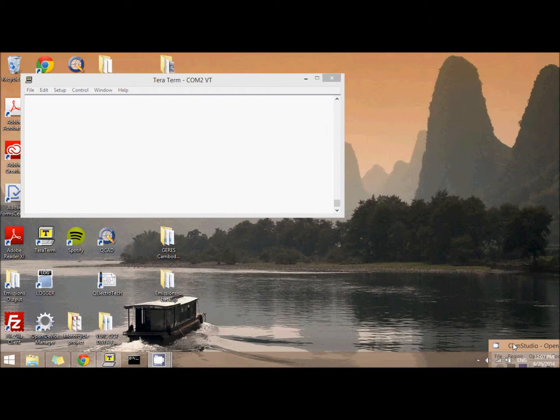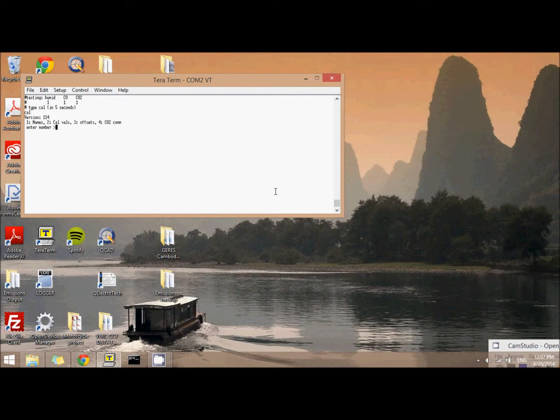So let's turn on our sensor box. In the first 5 seconds, we need to enter CAL and hit enter, and that gets us into calibration mode. If you forget to enter CAL in the right amount of time, you can reset your sensor box to have another chance to get into this calibration mode. And here we see our 4 menu options. Our first step is to go to menu option 2, the calibration value, and hit enter. And that'll give us a chance to see all the current calibration values that are entered into the sensor box.